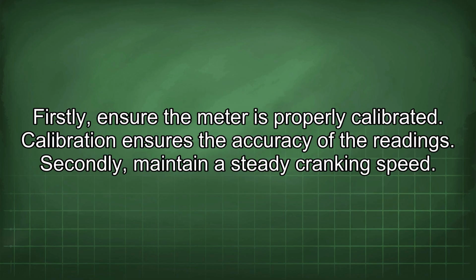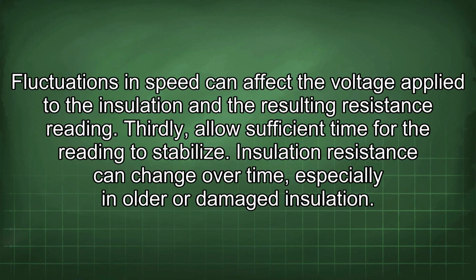Firstly, ensure the meter is properly calibrated. Calibration ensures the accuracy of the readings. Secondly, maintain a steady cranking speed. Fluctuations in speed can affect the voltage applied to the insulation and the resulting resistance reading.